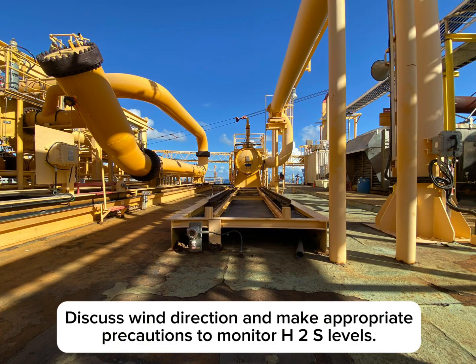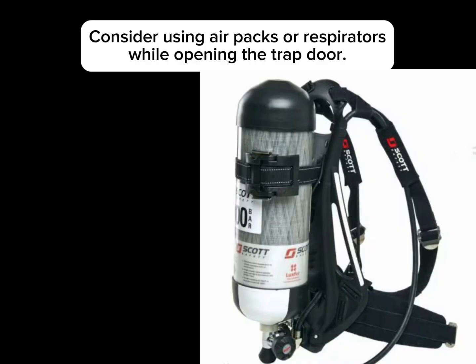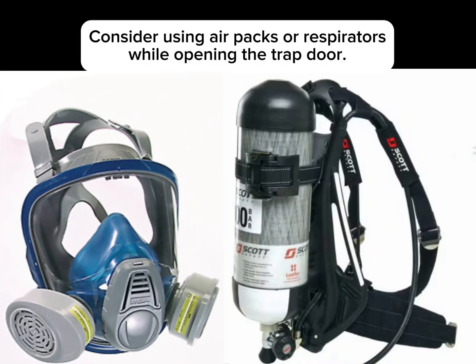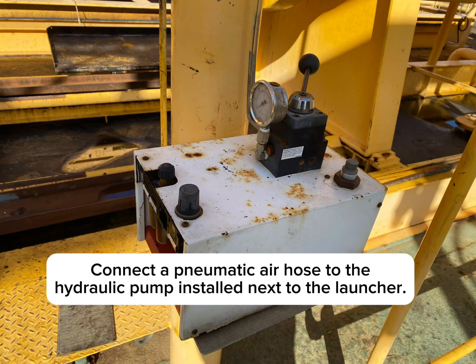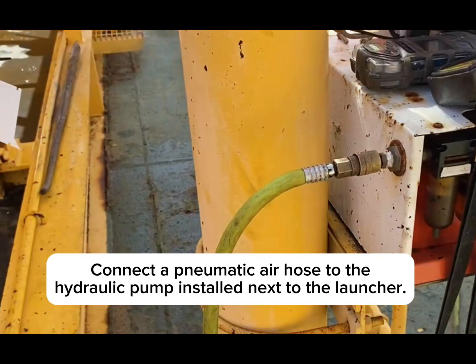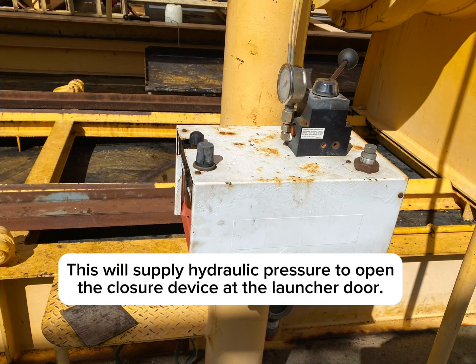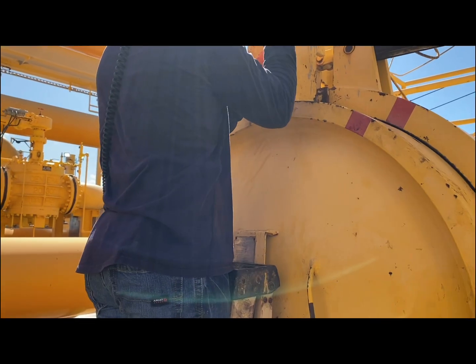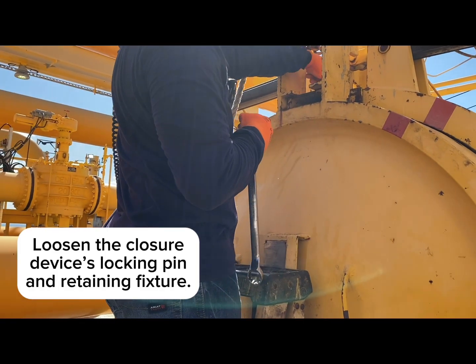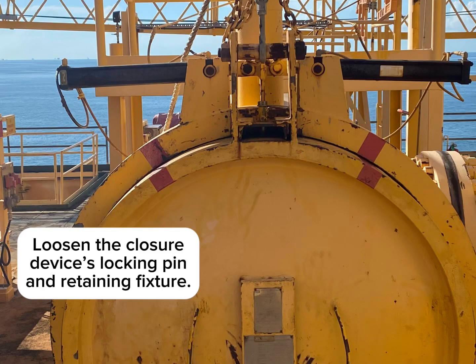Discuss wind direction and make appropriate precautions to monitor H2S levels. Consider using air packs or respirators while opening the trap door. Connect a pneumatic air hose to the hydraulic pump installed next to the launcher. This will supply hydraulic pressure to open the closure device at the launcher door. Loosen the closure device's locking pin and retaining fixture.